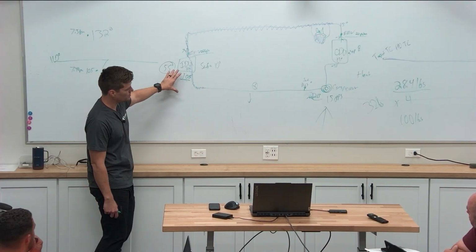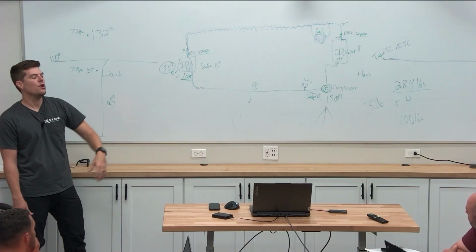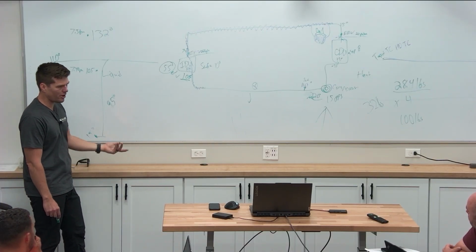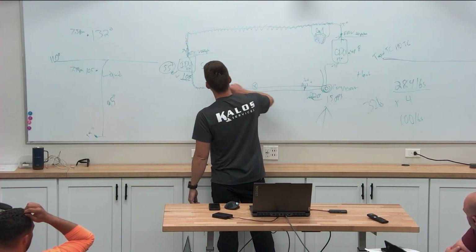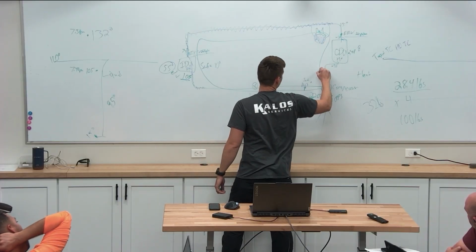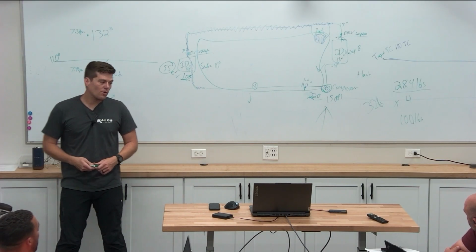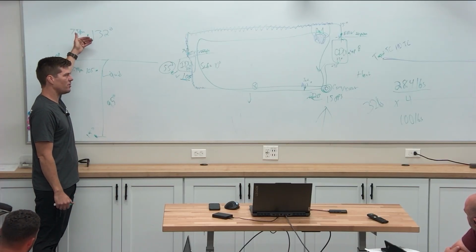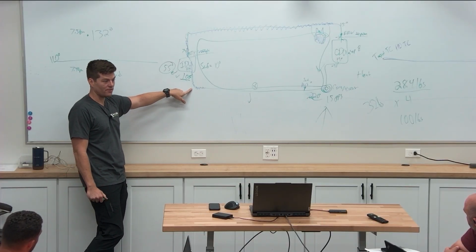And if this helps and you learn how to use this, you can either do it through the macros or you can draw it on a piece of paper, and you always follow the path of compression, right? It comes in here, it goes over here, it comes back, and it does this in a continuous loop. So now what I do is I find out where is it a liquid and where is it a vapor. Is it supposed to be a liquid there? No, it's not supposed to be a liquid here. It's supposed to be a vapor, right?